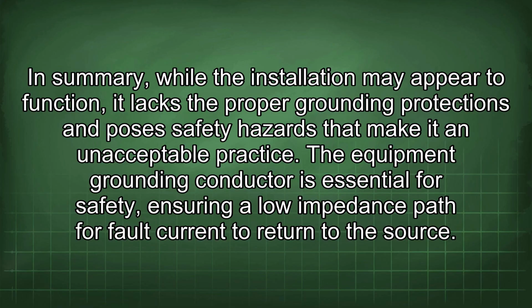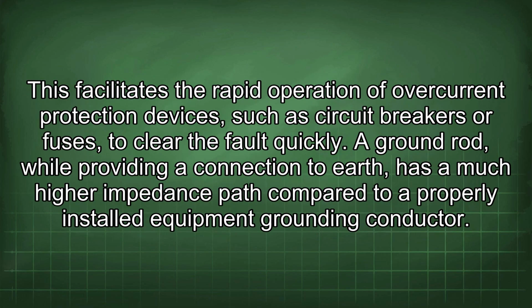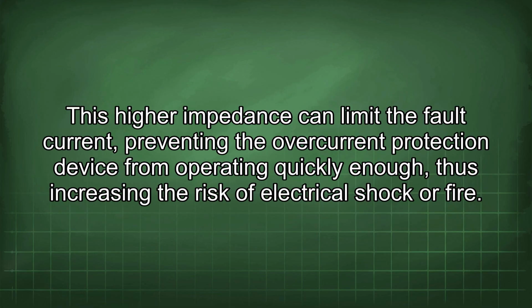The equipment grounding conductor is essential for safety, ensuring a low impedance path for fault current to return to the source. This facilitates the rapid operation of overcurrent protection devices, such as circuit breakers or fuses, to clear the fault quickly. A ground rod, while providing a connection to earth, has a much higher impedance path compared to a properly installed equipment grounding conductor. This higher impedance can limit the fault current, preventing the overcurrent protection device from operating quickly enough, thus increasing the risk of electrical shock or fire.